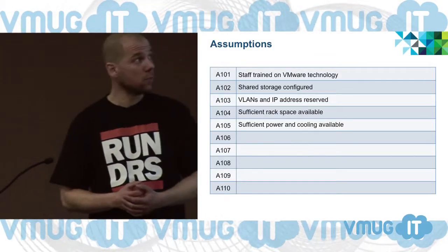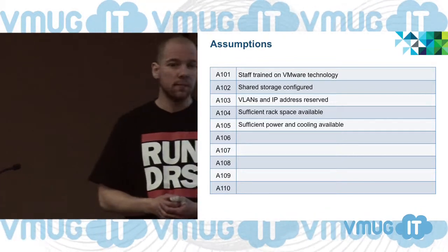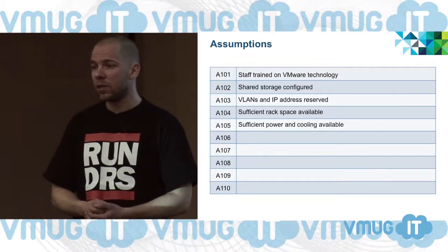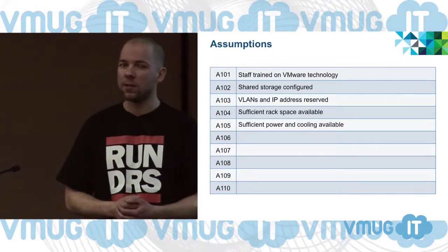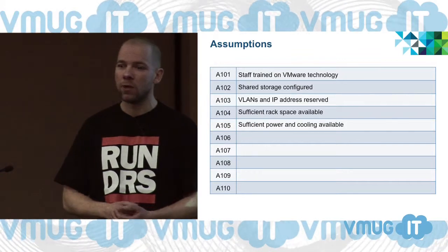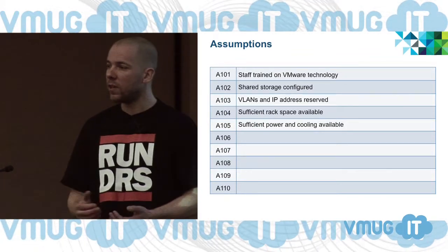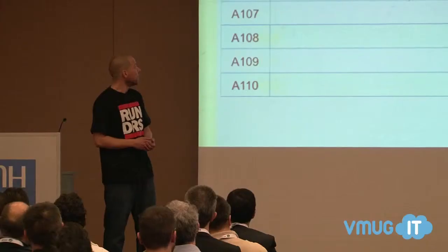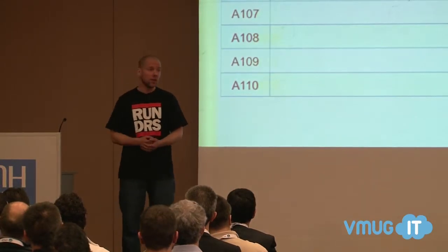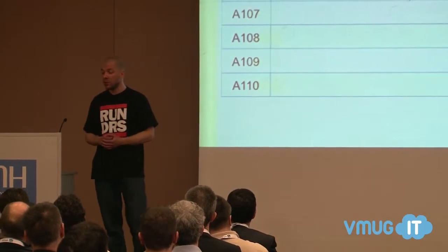Assumptions are things you haven't validated with your customer. A typical one is assuming sufficient power and cooling is available. I've seen people power on a VMAX only to find it's consuming a lot more power than expected and the whole environment goes down — or there's only one power line coming into the building, and if there's a power cut the whole data center freezes. I've seen that happen at hospitals, which is not pretty. Sufficient rack space available is another assumption that should actually be validated.